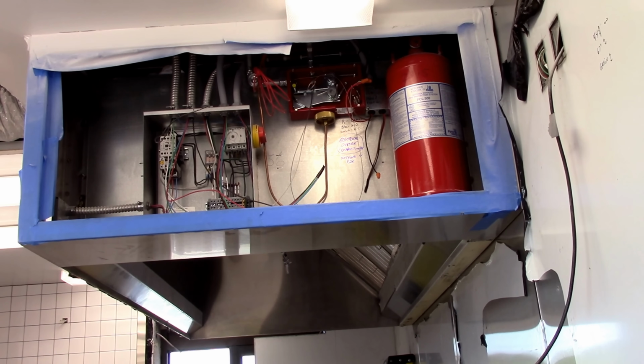I was going to let you know we've got two wires going to our smoke alarm system. Our smoke alarm system has a normally closed circuit, and when that opens in case of a fire, the unit's going to shut off. So I want you guys to see what we got going on here. I'll go ahead and show you.